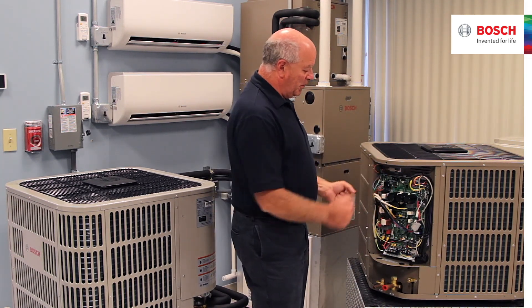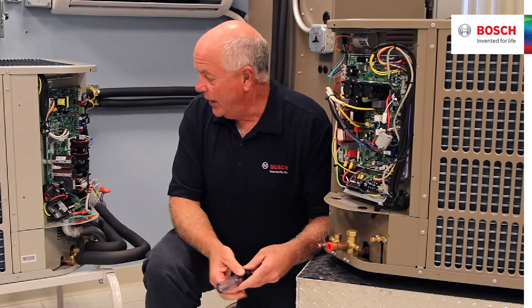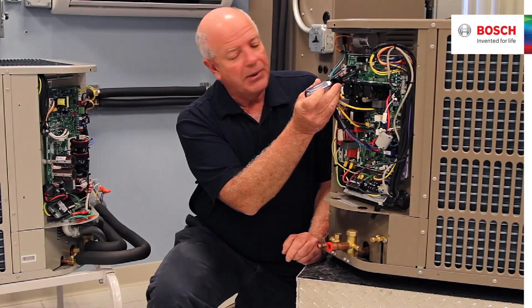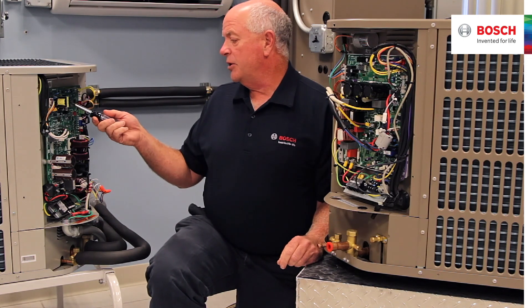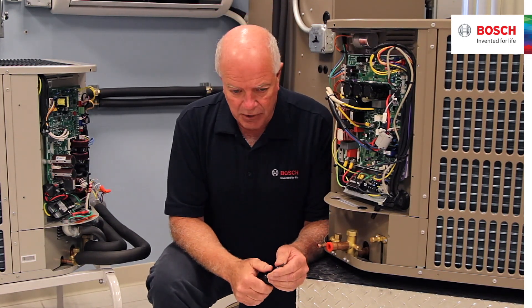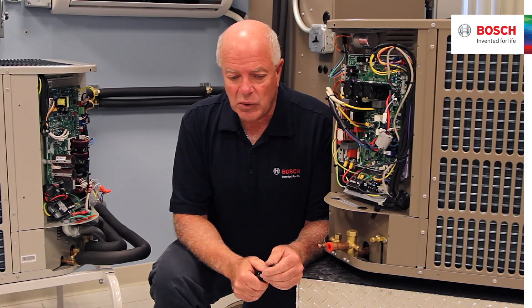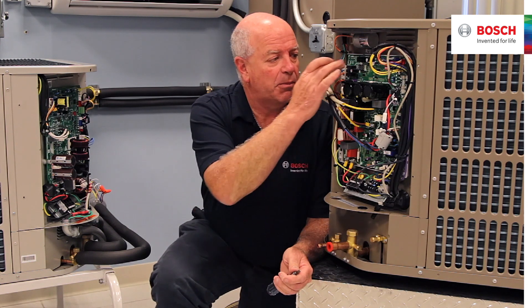There's nothing on this board that's really replaceable, nothing that can be interchanged. What makes these units a little bit unique is that we have a display up here on this one, and a display on this one as well. Our display on this unit is going to give you head pressure, suction pressure, compressor speed, fault codes, and outdoor ambient. All those sensors are processed through here.